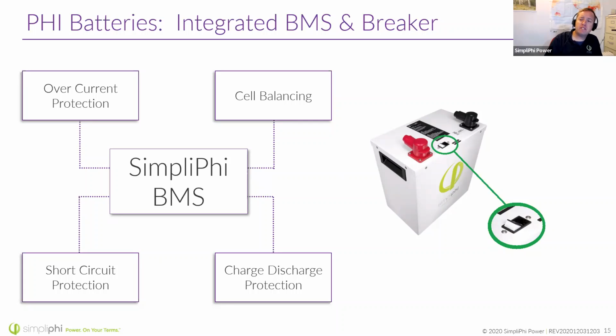It's giving you overcurrent protection, short circuit protection, charge and discharge protection. Really, it's made to keep the cells balanced. The battery management system, you could think of as the last line of defense. It's not there to change or regulate power going in and out of the battery. What we want to see is a properly sized system and a properly programmed system. That battery management system is really there for cell balancing, but can be a last line of defense.